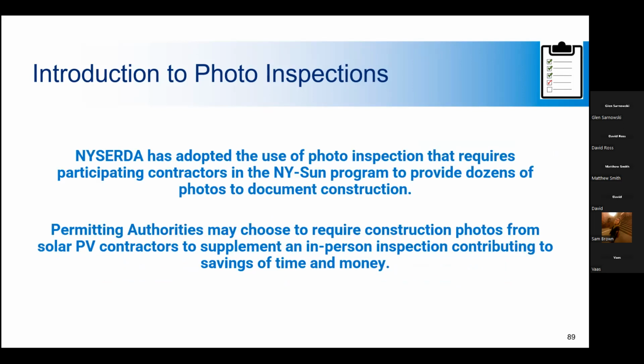NYSERDA has been doing these types of photo-only inspections for a long time now. Permitting authorities can choose to require photos to supplement an in-person inspection to avoid making multiple trips to a site and to save time and money. Photos can tell a story of how things were constructed and save the inspector time. It also improves inspector safety by reducing exposure to hazards like ladders and energized electrical equipment. The contractor may include photos of trenches and walls before being closed up to reduce the number of trips required for a code inspector.